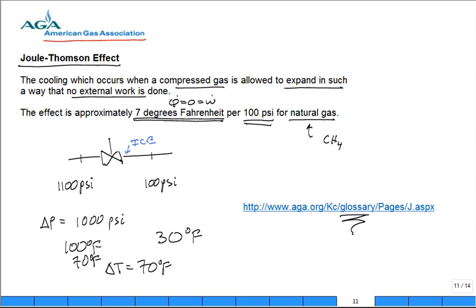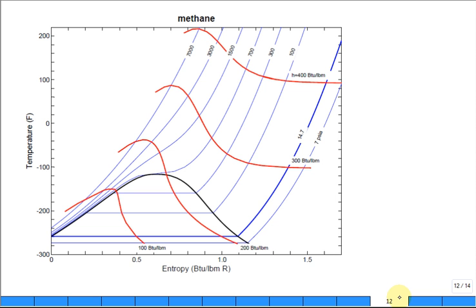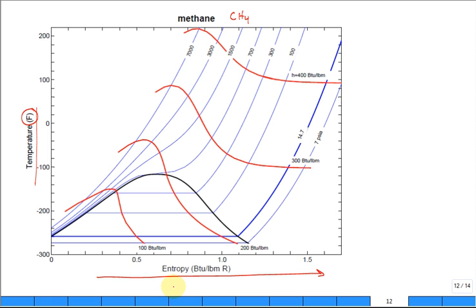It starts to deposit that water right there and build up ice. You decide to go open it and you don't get the flow because it's plugged. Let's see about understanding this with the temperature-entropy diagram for methane. We have temperature in degrees F and entropy in BTUs per pound mass degree R. What is this point right up here? Critical point. The temperature for methane's critical point is around negative 116 degrees F.